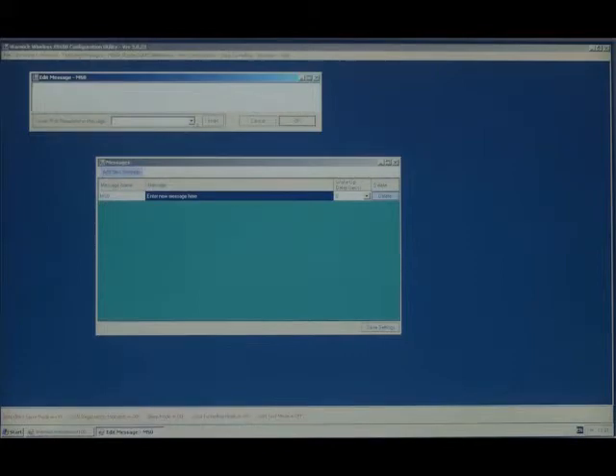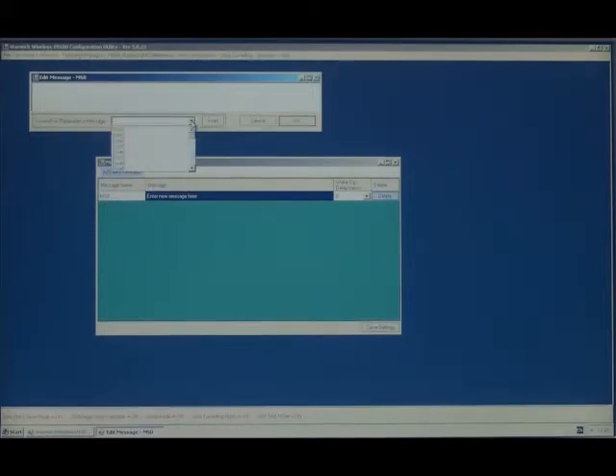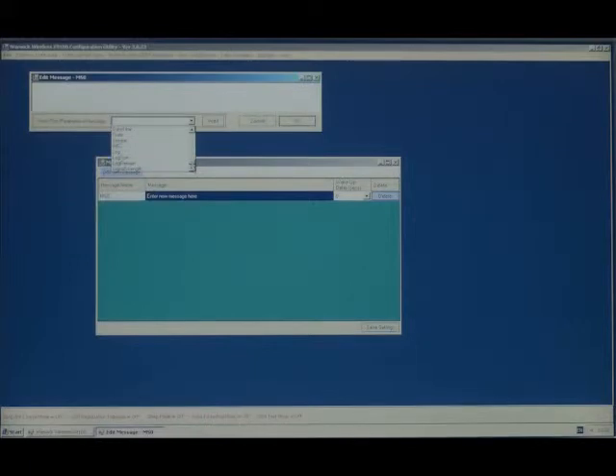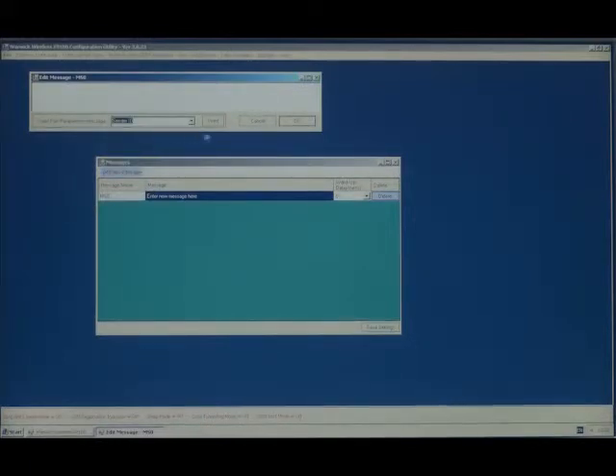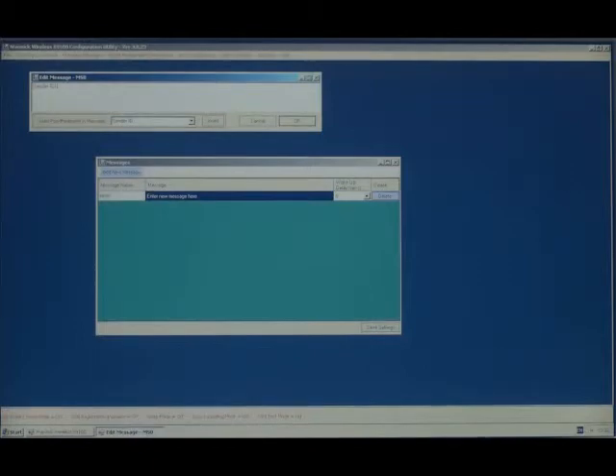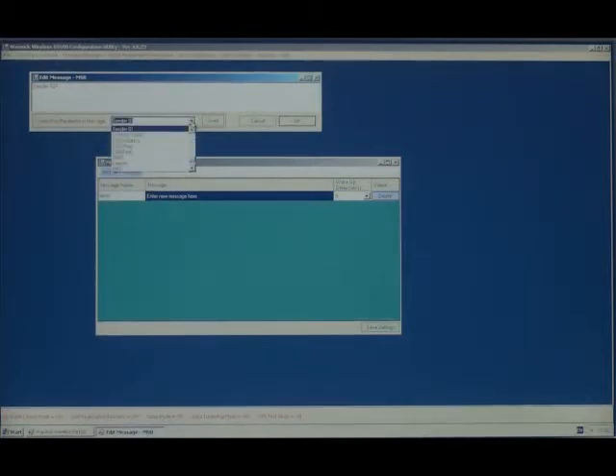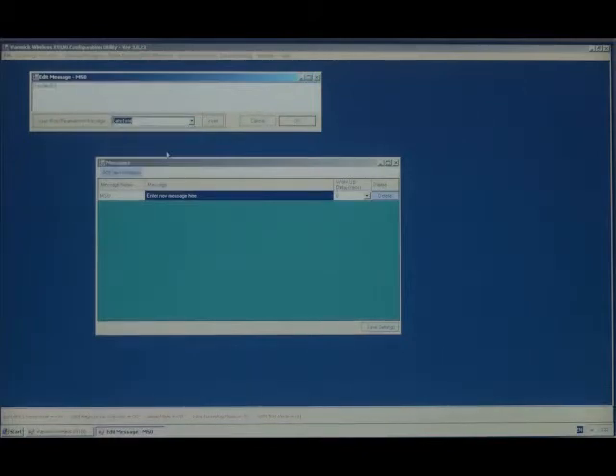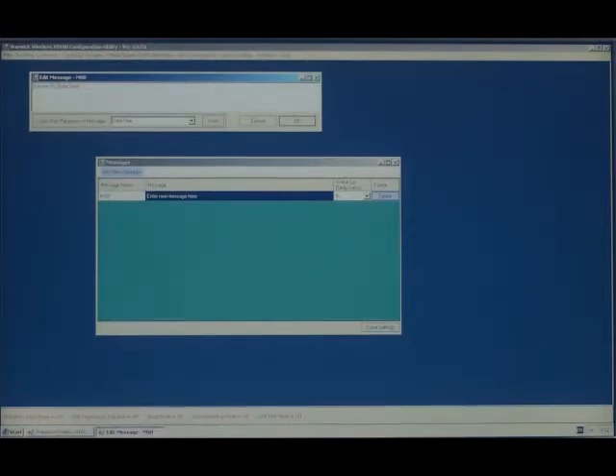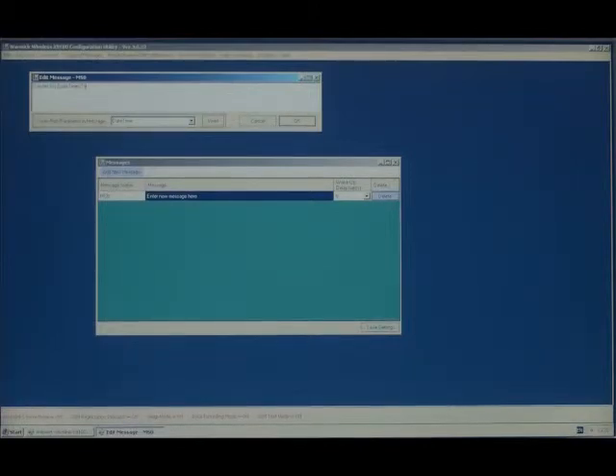The first thing to do is click on the drop down menu and select the sender ID. This is a unique number allocated to each X9100 and will identify where the message came from. The next thing is to enter a time date stamp, which will be inserted by the real-time clock when the message is sent. We then type in the message tank level.